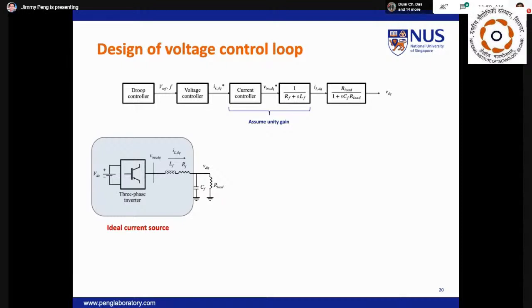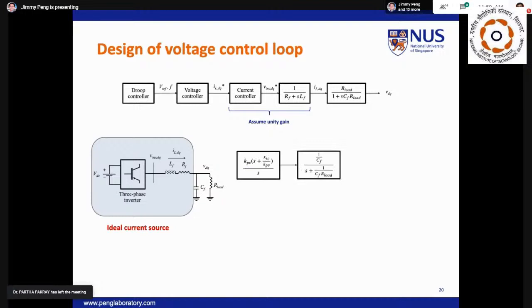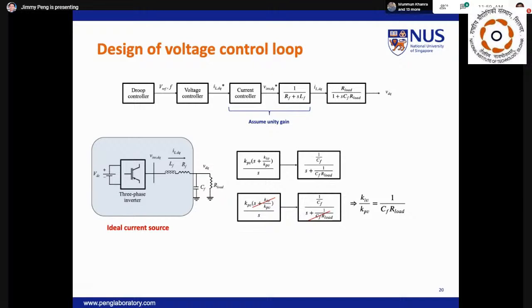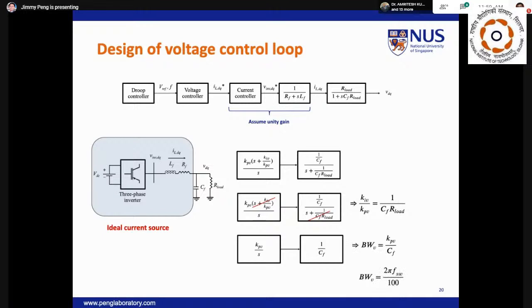The objective of the voltage control loop is to define the current reference for the current control loop. Assume the three-phase inverter is behaving like an ideal current source, and the well-designed current loop is ideal with a unity gain. The transfer function of the voltage controller to the output VDQ takes the following form. We can make the ratio KIV divided by KPV equal to 1 over CF times the R load to simplify the transfer function. As a result, the control bandwidth of the integrator will become KPV divided by CF. To ensure adequate timescale separation from the current controller, we need to make sure the control bandwidth is around 2 pi times the switching frequency divided by 100. Using the same procedures as before, we can design the gains of the voltage controller accordingly.